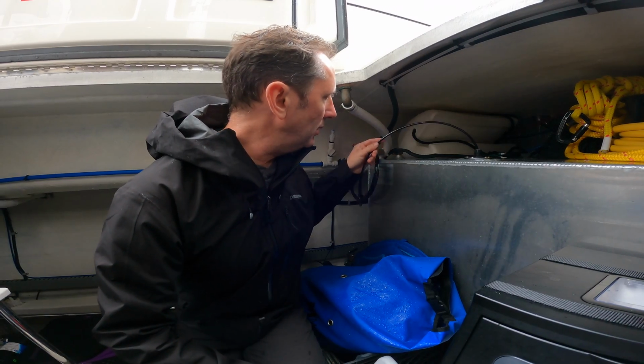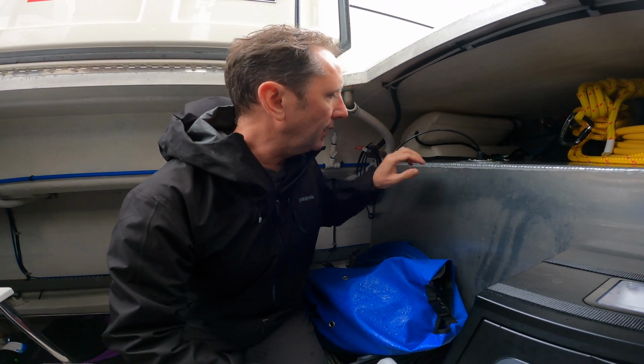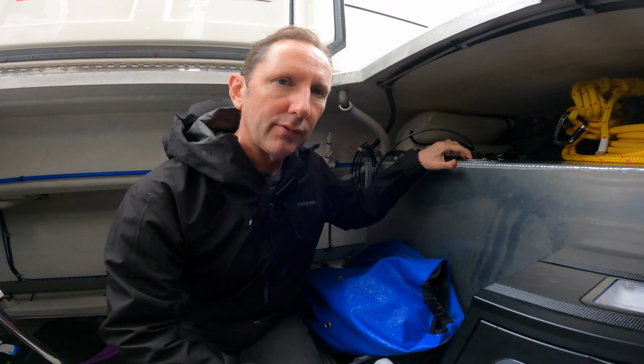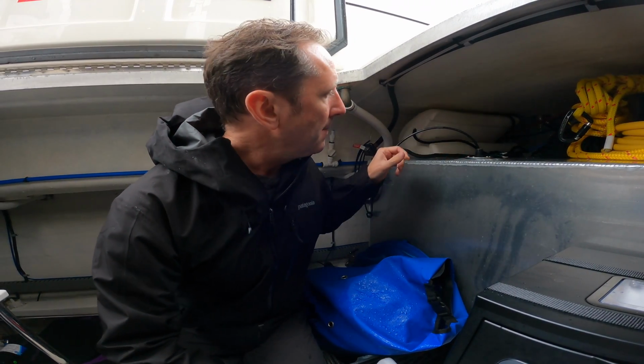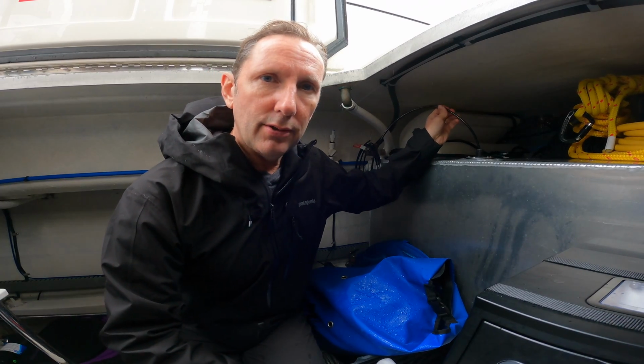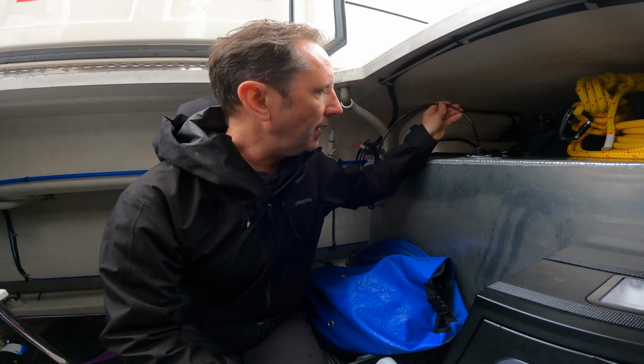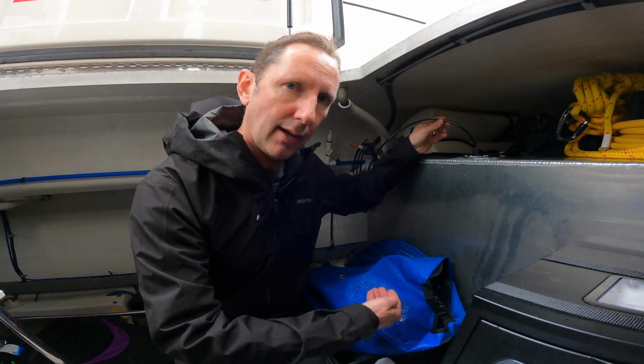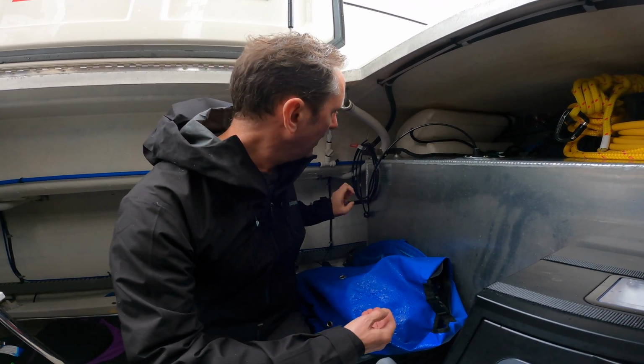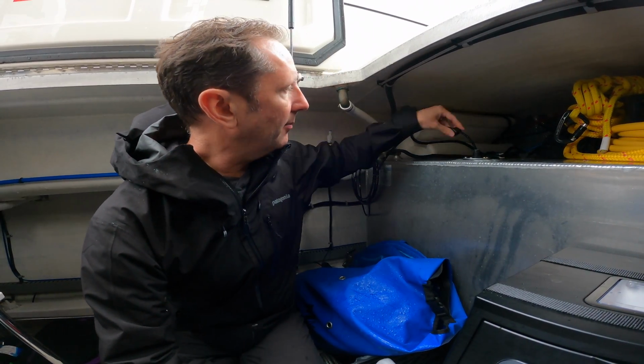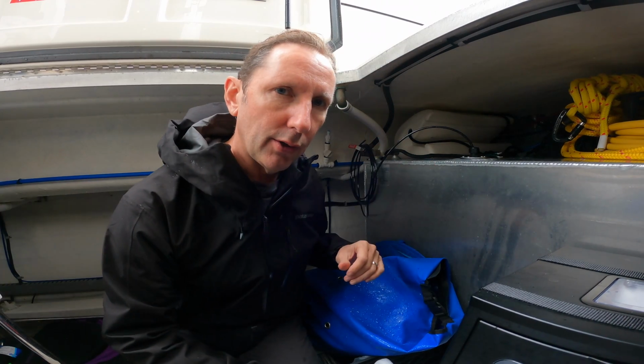This is the new transducer. We've got the gland that now goes into the SAE 5-screw standard fitting. The transducer just drops to the bottom of the tank, and we want to get it to slide to the back of the tank as much as possible, then run this gland back up and tighten it off. And then we'll have our new sensors.